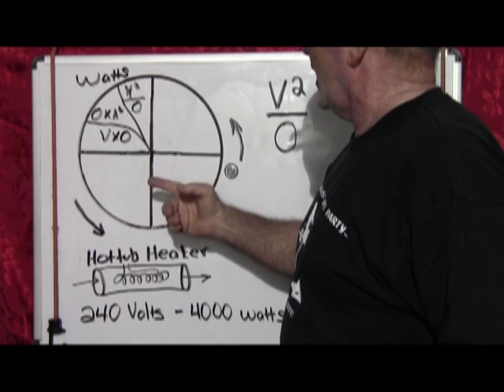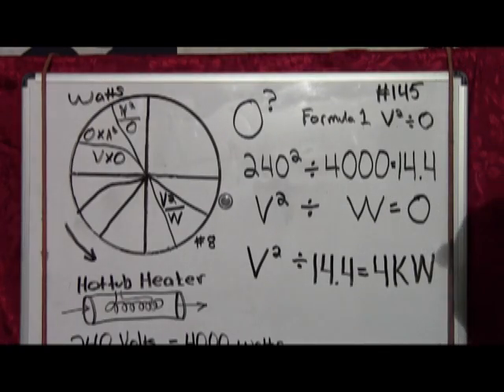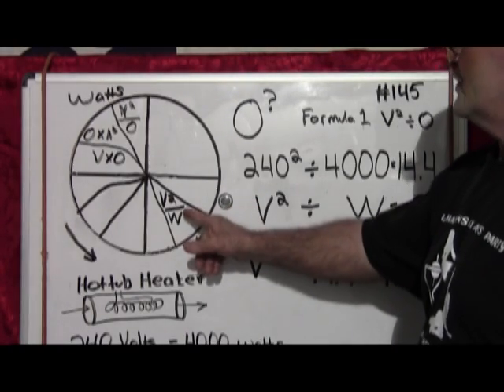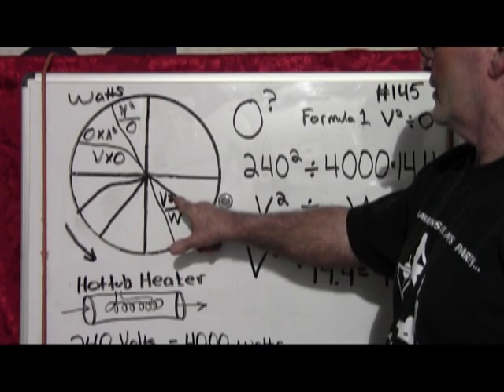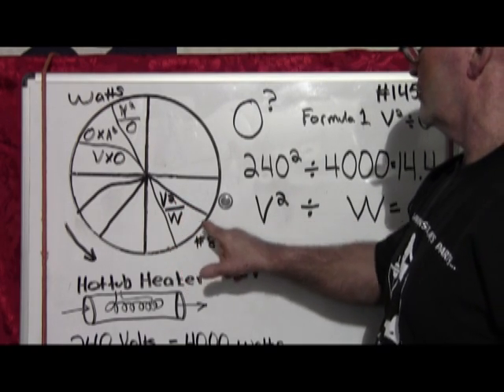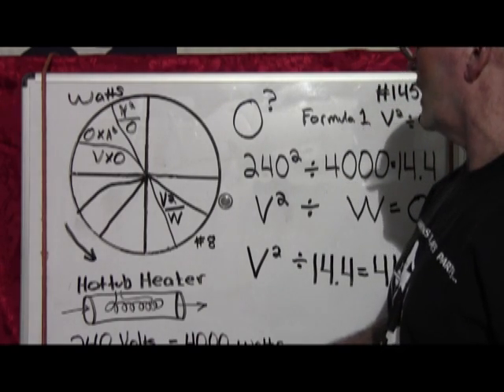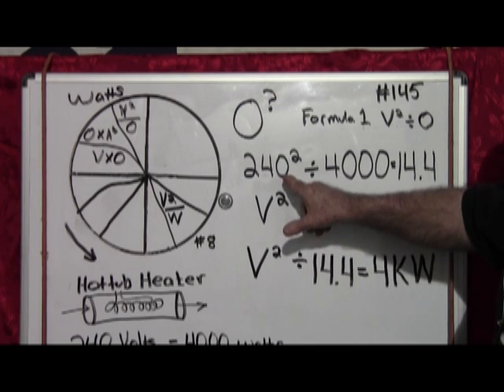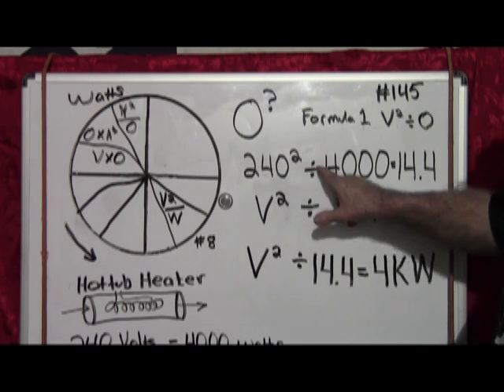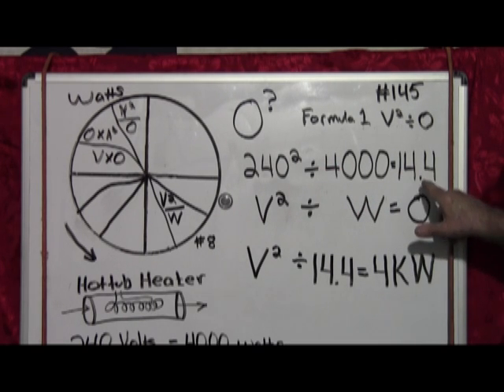Because with any two factors on this pie chart, you can figure for all four factors: watts, amps, volts, or ohms. So we're going to borrow from the ohms section, actually number 8, volts squared divided by watts will give you ohms. We've got volts and we've got watts. So you take 240 volts and square it, divide that by 4,000 watts, you get 14.4 ohms.